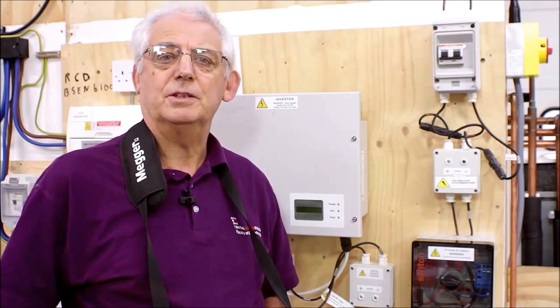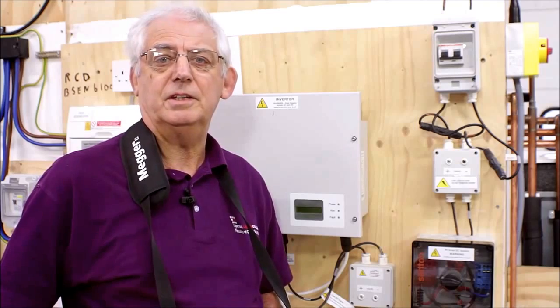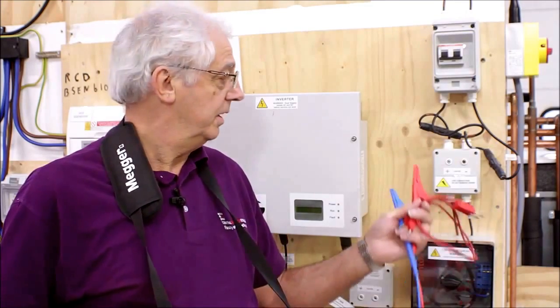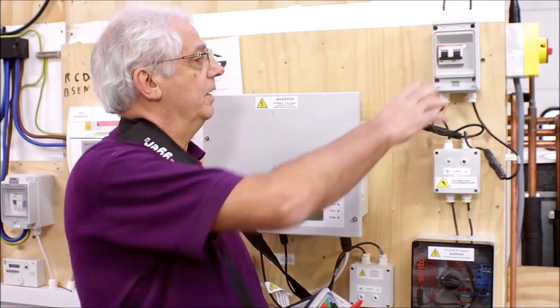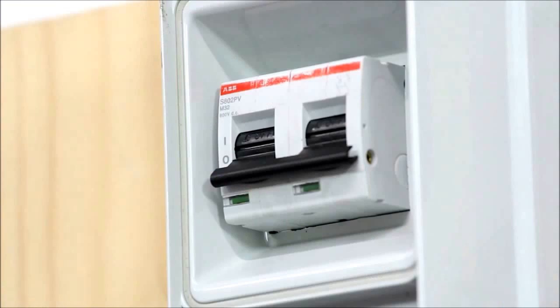Once you've installed a photovoltaic system, it's important that you carry out a range of tests to make sure that everything is absolutely safe, because, as you know, PV is DC, and DC inside a building can cause all sorts of problems unless it is put in very, very carefully. What we've got here is a rig that we've made up just for testing and to explain to people how the system works. We've got a main isolator up here, which is really for our use, and the instructors would use that to isolate the whole of the system.